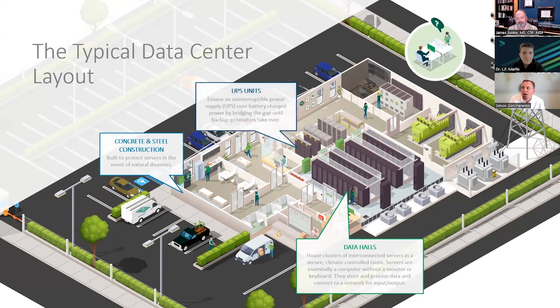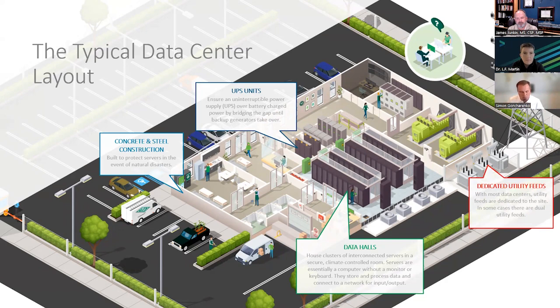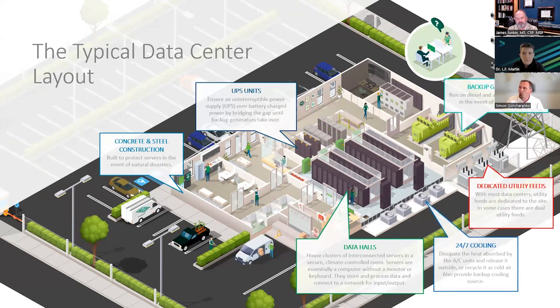Then you've got UPS units, uninterruptible power supplies, basically a string of batteries a little larger than a car battery, all connected together and constantly charging. A power feed comes in from the utility, the dedicated utility feed, often with two independent feeds. In case of a loss of power, a switching mechanism within the data center switches power from the utility to backup generators. The UPS units function to keep carrying the load while that switching takes place. Typically a data center has enough batteries in these UPS units to maintain power for 15 continuous minutes, though they don't really need that much since switching from utility to generator usually takes just seconds.